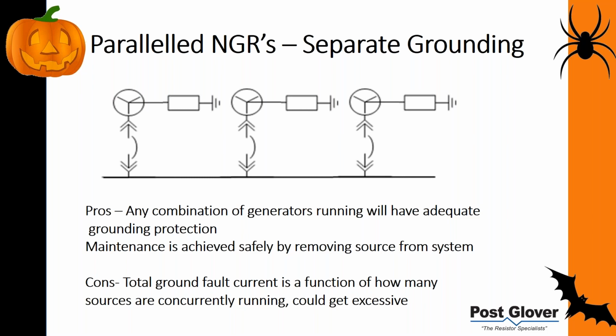Let's say you had 200 amps for each generator. In this picture right here, you'd have a total of 600 amps of ground fault current. That in itself probably wouldn't be an issue, but let's say you had 10 of these things—you may need to go for a different, either much lower current or a different methodology here.